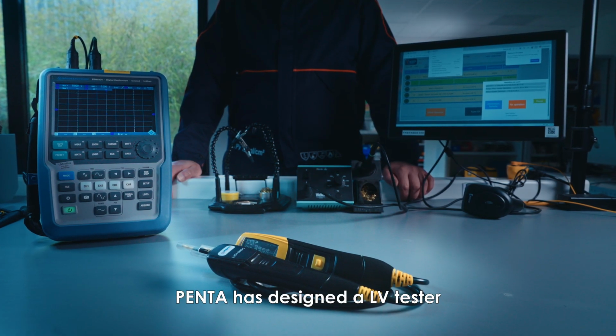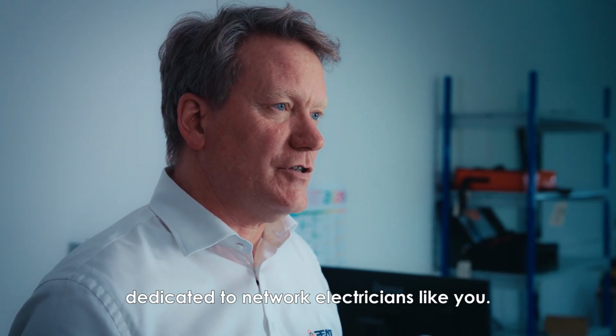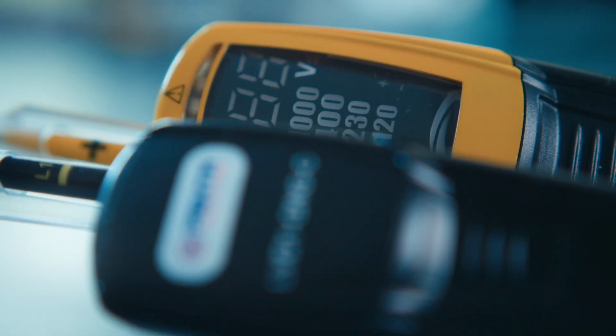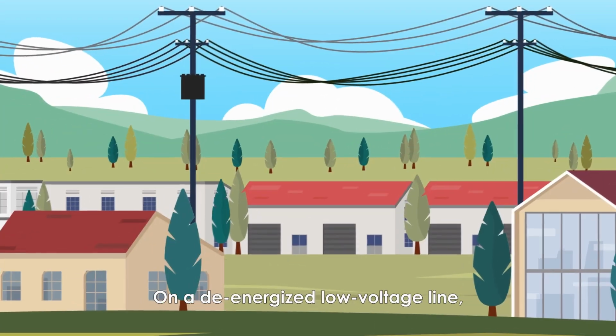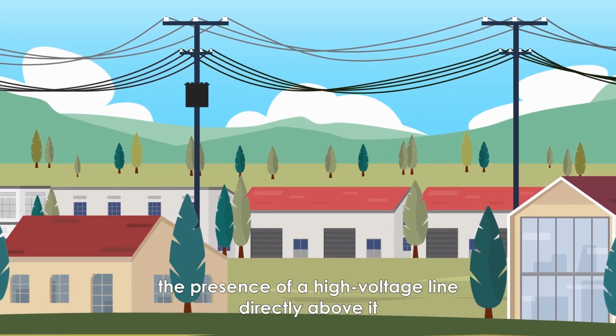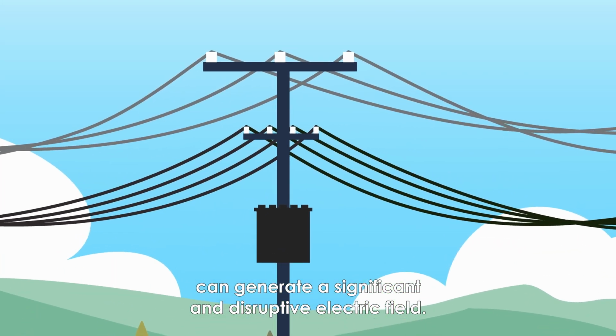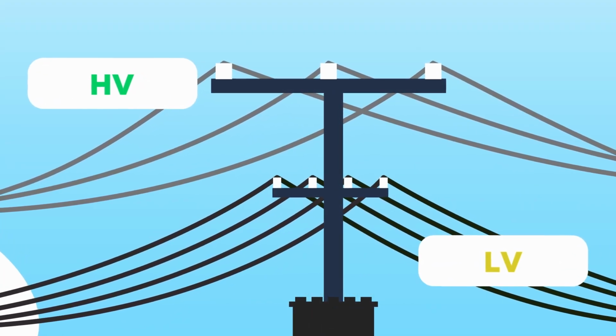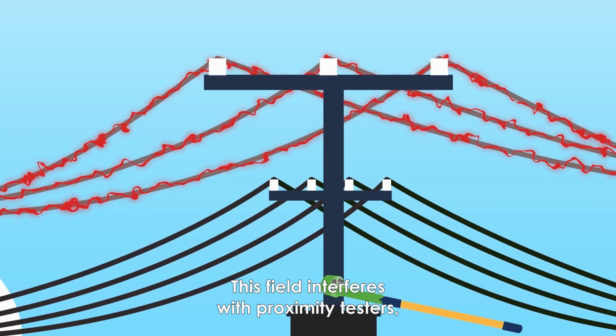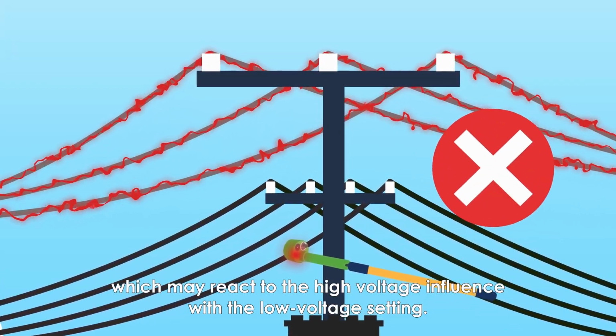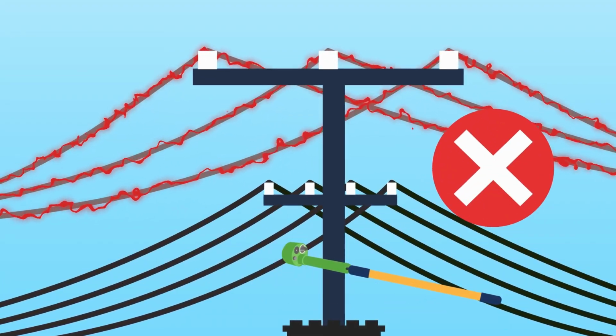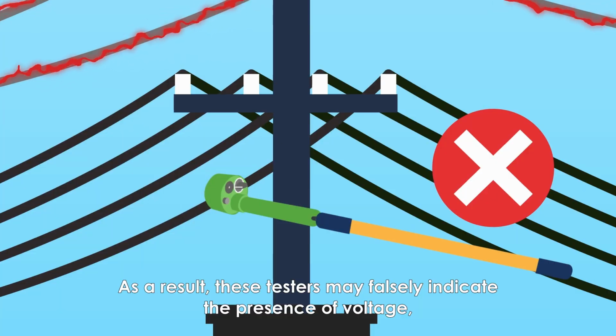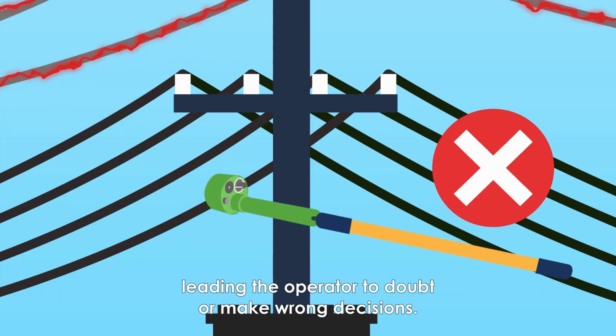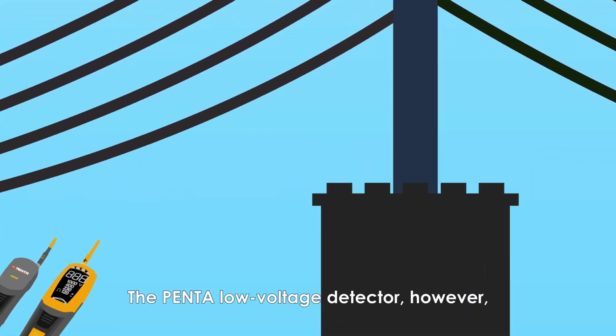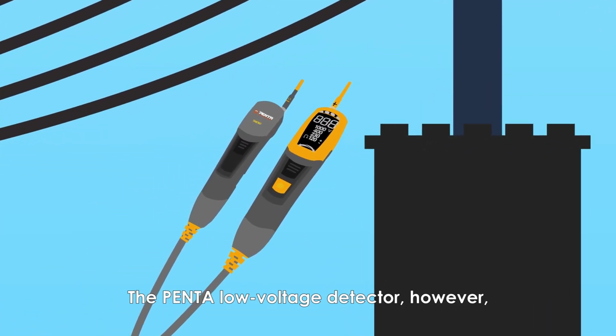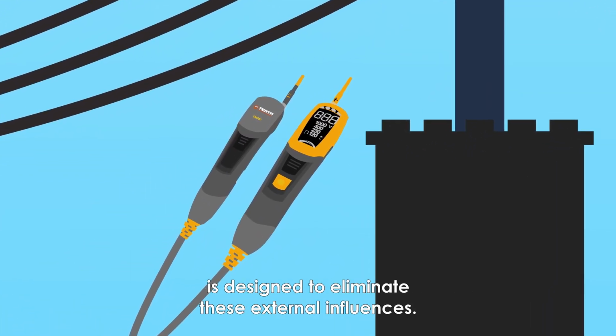Penta has designed a low voltage tester dedicated for network electricians like you. On a de-energized low voltage line, the presence of a high voltage line directly above it can generate a significant and disruptive electric field. This field interferes with proximity testers, which may react to the high voltage influence with the low voltage setting. As a result, these testers may falsely indicate the presence of voltage, leading the operator to doubt or make wrong decisions. The Penta low voltage detector, however, is designed to eliminate these external influences.